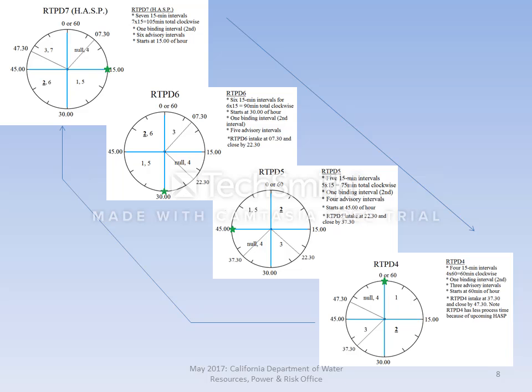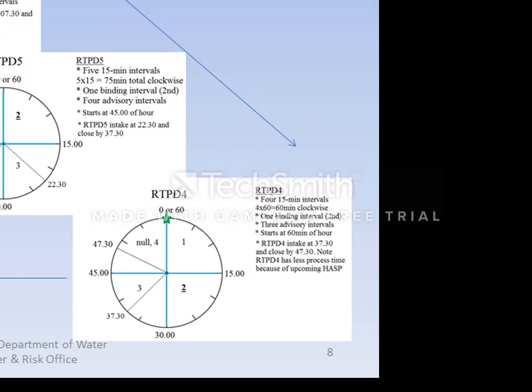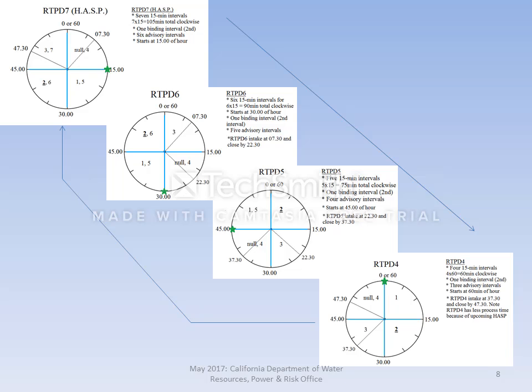PD4 samples inputs at the 37:30 mark of the hour. Note this is less available computation time due to the upcoming HASP. PD4 performs iterative computation to identify the most optimal feasible unit commitment solution, publishing four 15-minute market results no later than the 60-minute mark, made available through ADS and OASIS. PD4 produces four 15-minute intervals for 60 minutes total. Instructions commence at the 60-minute mark, and only the second 15-minute interval — between the 15 and 30-minute marks of the next hour — is binding. Intervals 3 and 4 are advisory.